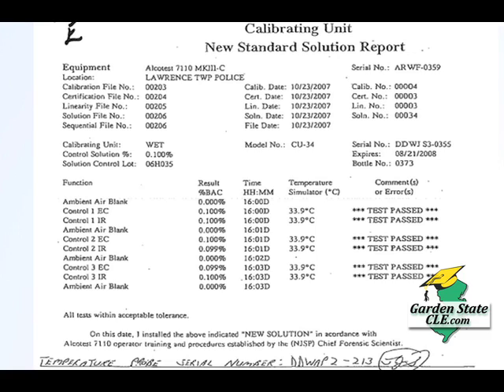New standard solution report. This one is at the time of calibration. So the calibration date and the file date are going to be the same. The sequential file number, again, should just be one higher than the linearity tests. It's got everything else in here. The thing that you're going to look for specifically is the temperature probe serial number. This is the temperature probe that is kept at the police department. This is not the black key one that the coordinator brings. They're using the police department's own bottles, their solution bottles and their own temperature probe, which gets left on the instrument.